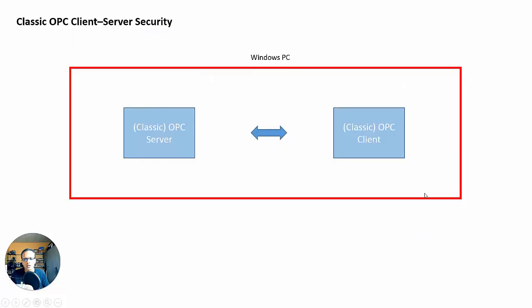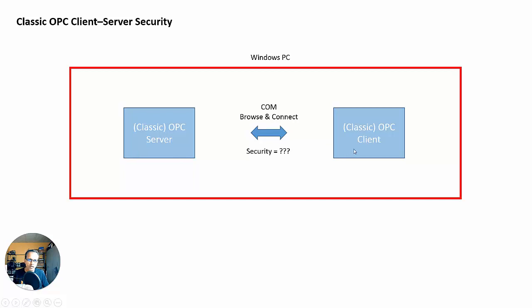With classic OPC, the security is basically questionable — almost no security in it. As I told you in the previous video, in order for an OPC client to connect to a server, it's just browse and connect. There's no username and password, there's no encryption, there's nothing. That was okay because classic OPC was usually running on the same Windows PC on the plant network, there was an air gap — no physical connection between the plant network and the IT network — and only certain people could get in front of the PC running this stuff. So it was secure in that way.